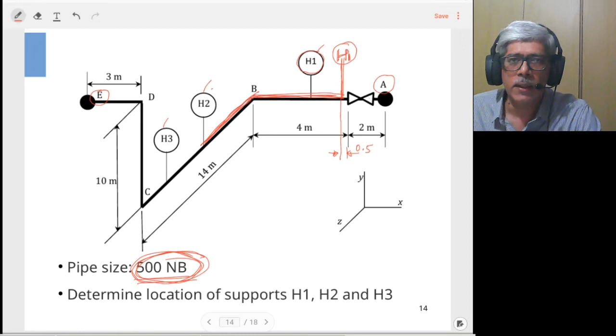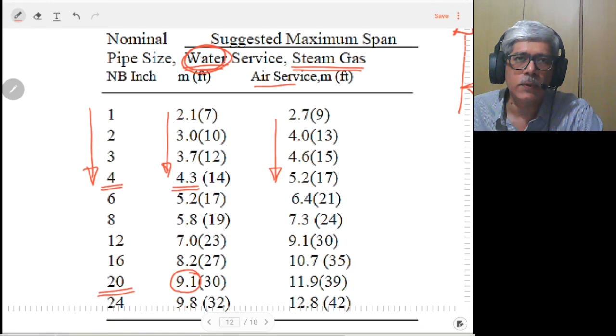So 500 NB corresponds to 20 inches. So we have to just divide by 25. That will give us the inch size. So our pipeline is 20 inches, and assuming that this is a water service, we will provide a maximum span for a straight pipeline of 9.1 meters. So the straight span is given as 9.1 meters.